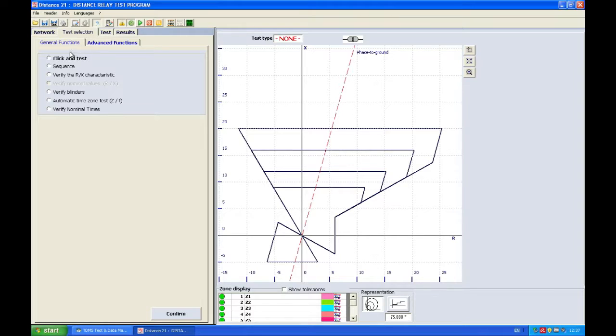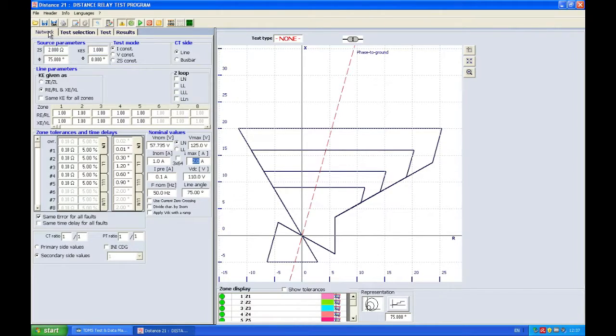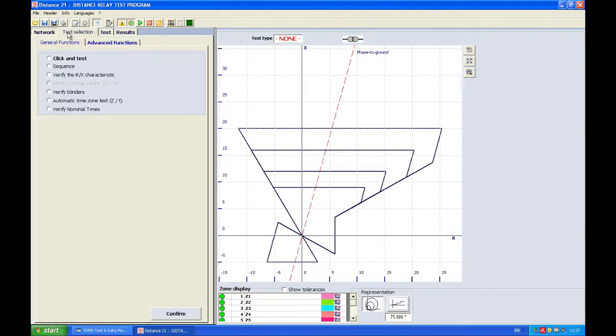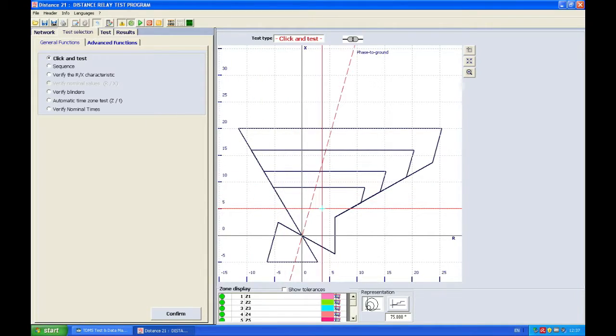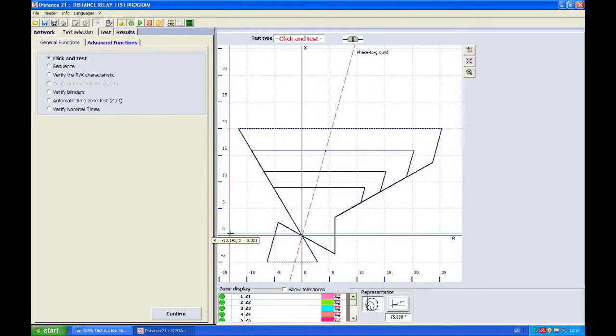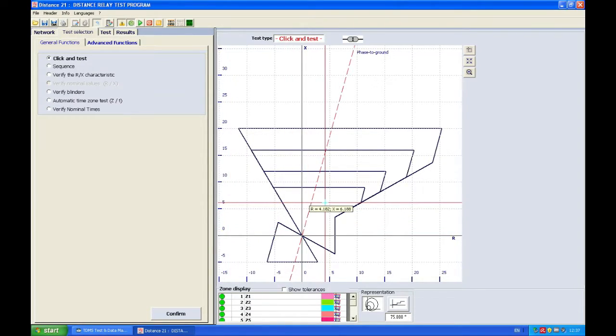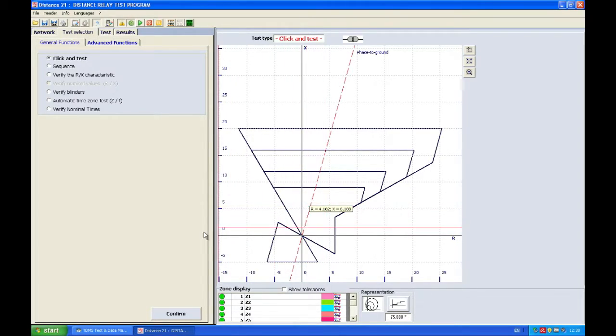So I'm going to choose first of course from network, I go to test selection and I choose general function tab, and in general function tab I choose click and test. So with click and test when I click, the DRTS will generate the currents and the voltages which I need in order to trip the relay.